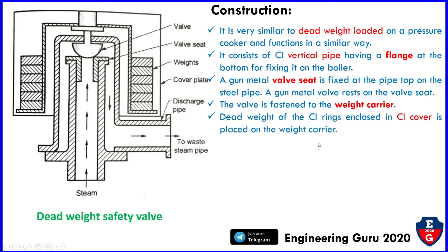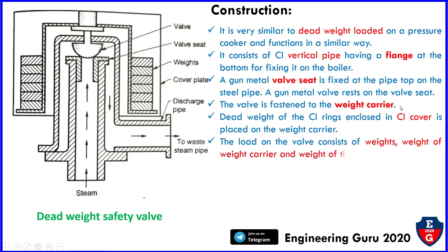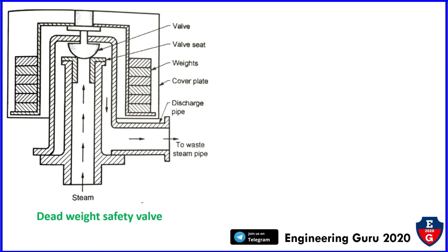A dead weight of cast iron rings enclosed in a cast iron cover is placed on the weight carrier. Here we can see the cover plate, the weight, and the cast iron cover. The load on the valve consists of the weights, the weight of the weight carrier, and the weight of the valve itself. This is the construction of the dead weight safety valve.